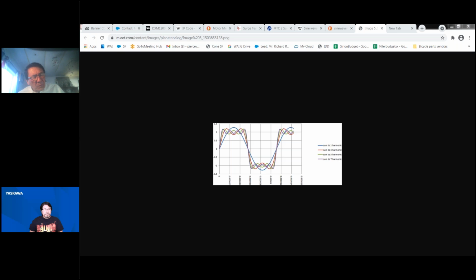We have a filter. And I think that the motor shops didn't come back to us with correct autopsy data. They were kind of rubber stamping DVDT voltage spike whenever they had a failure on a VFD. And then we started to look into it and we realized, no, these are thermal failures. As Craig said, they split open a motor. He looked at it. He saw the standard and classic evidence of a thermal issue.